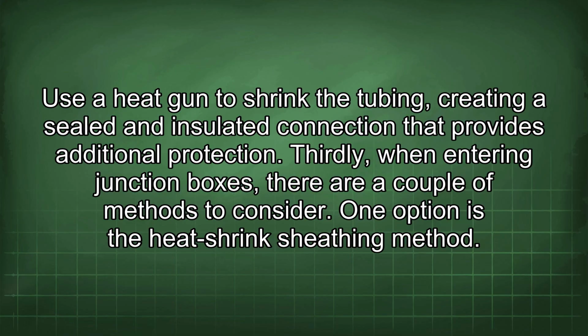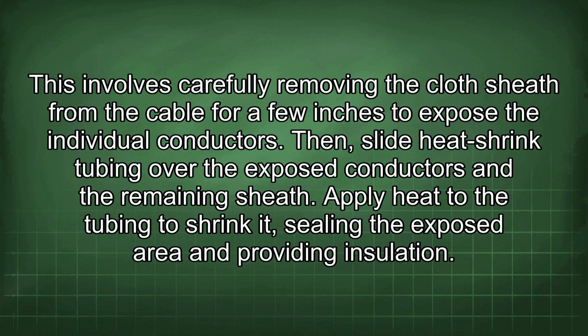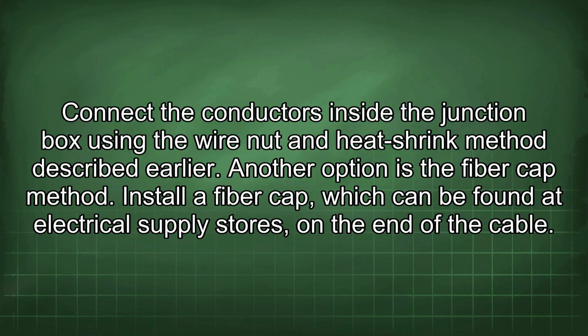One option is the heat shrink sheathing method. This involves carefully removing the cloth sheath from the cable for a few inches to expose the individual conductors. Then slide heat shrink tubing over the exposed conductors and the remaining sheath. Apply heat to the tubing to shrink it, sealing the exposed area and providing insulation. Connect the conductors inside the junction box using the wire nut and heat shrink method described earlier.